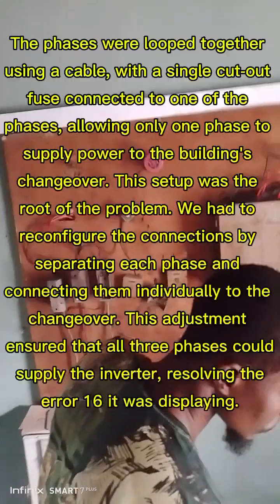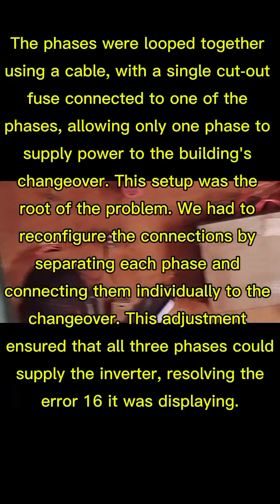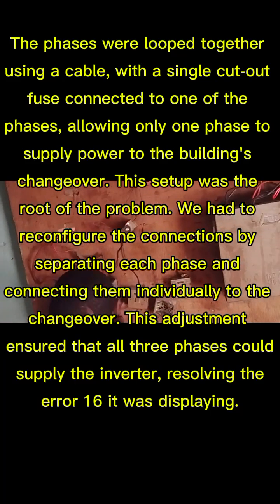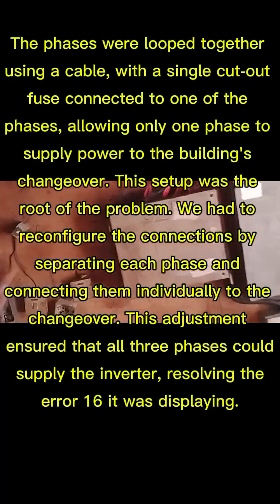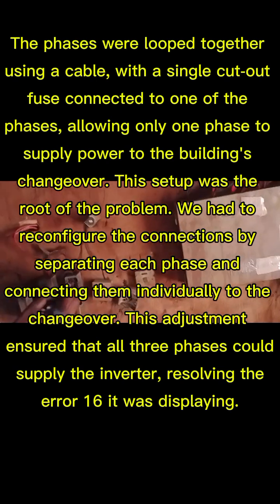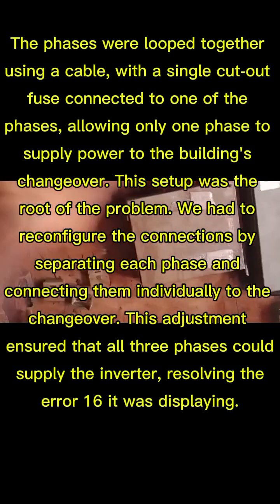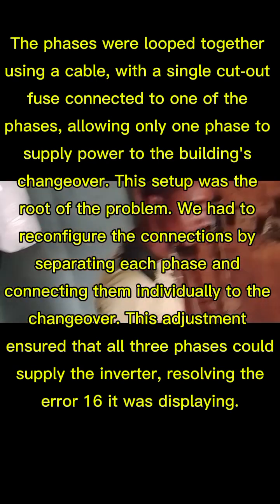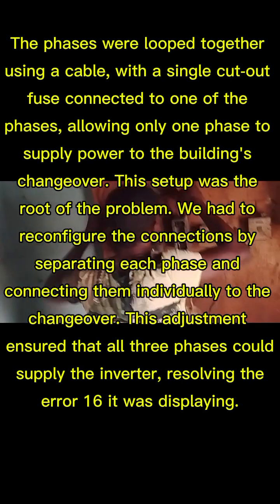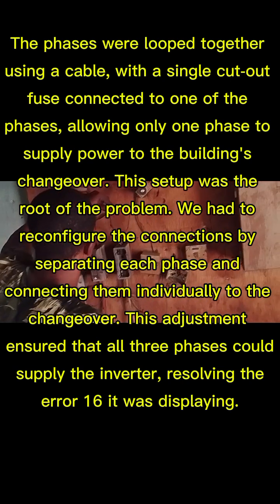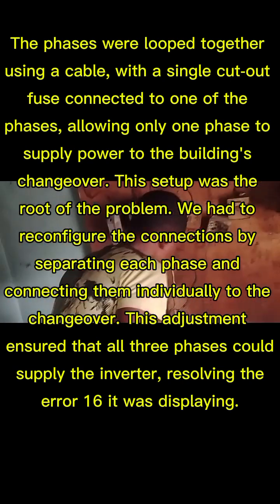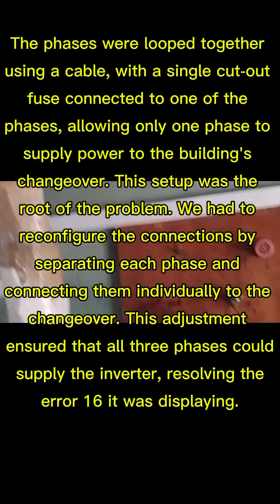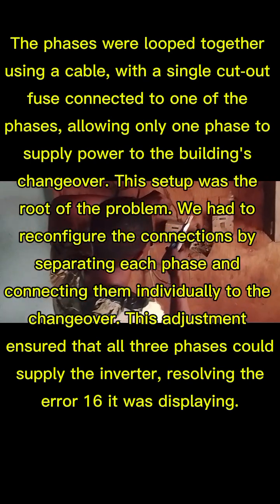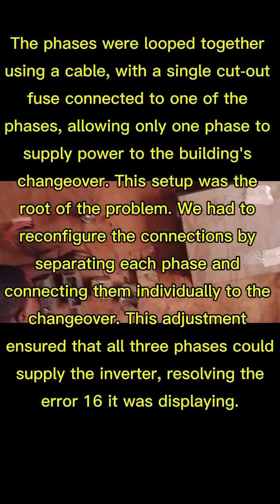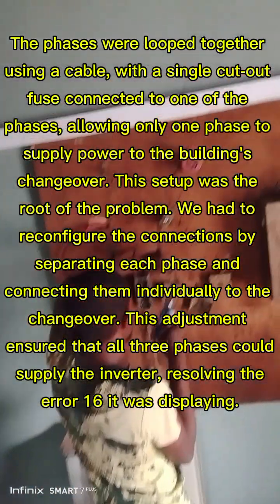So we now discovered that the issue we were having here is that the phases were looped together using a cable with a single cutout fuse connected to one of the phases, allowing only one phase to supply power to the building's changeover. This setup was the root of the problem. We had to reconfigure the connections by separating each phase and connecting them individually to the changeover. This adjustment ensured that all 3 phases could supply the inverter, resolving the error 16 it was displaying.